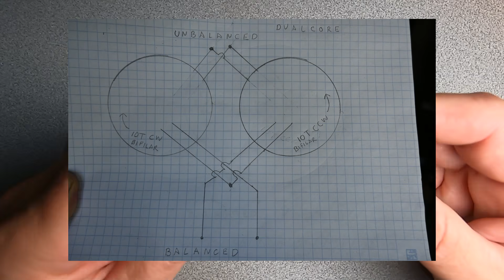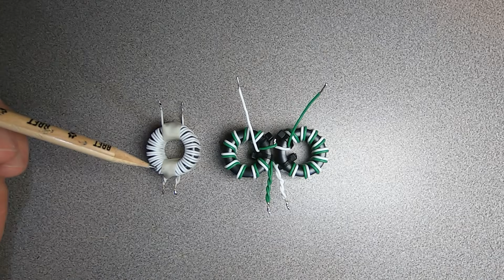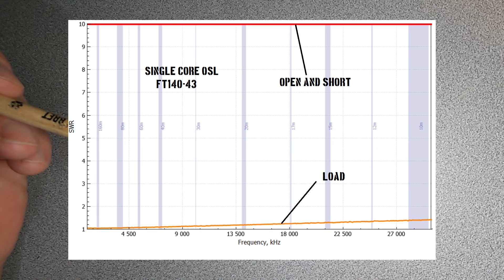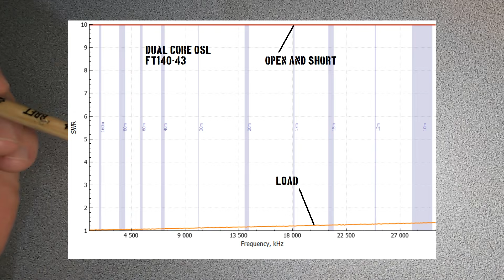So why am I comparing these two transformers to one another? It would be pretty clear that this would be a much simpler transformer to manufacture and cost less money, and perhaps that's the reason why it's selected more often than this variant. Both examples are almost identical in an open, short, and load test, as shown here. The transformers, when loaded, are transforming, and in conditions of open and short, they are both off the chart, which is exactly what we want to see.